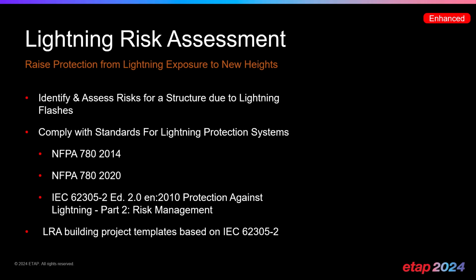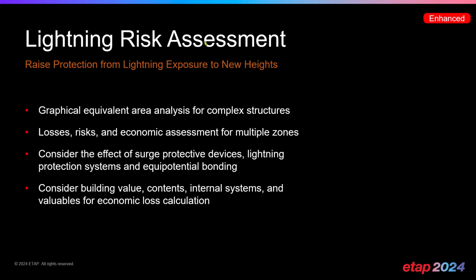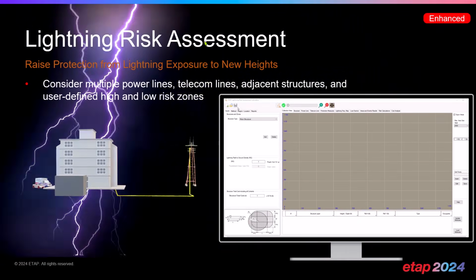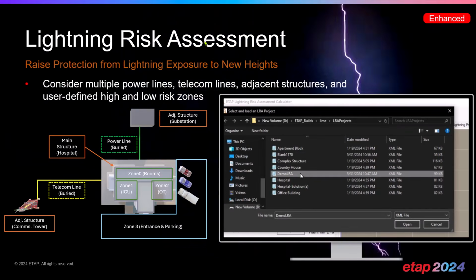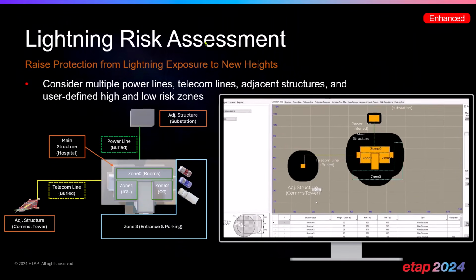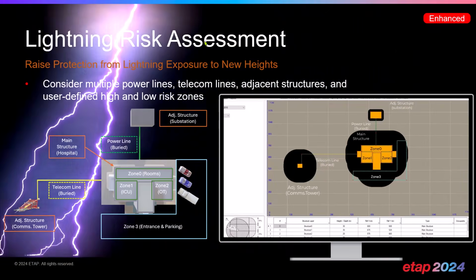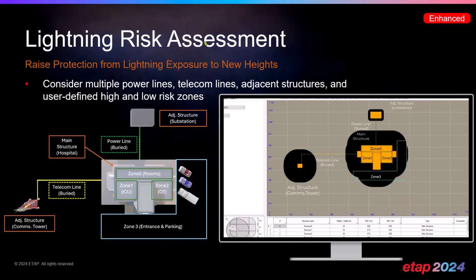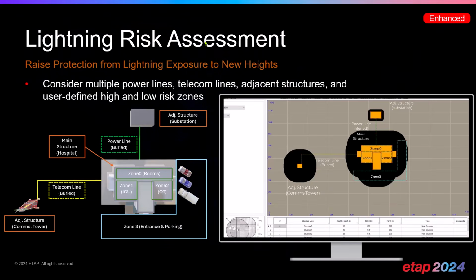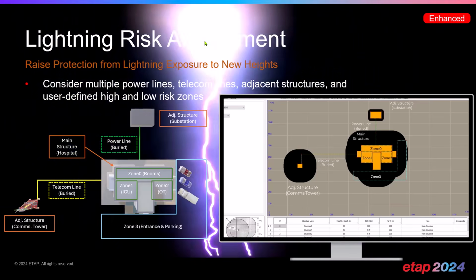And we also have project templates now based on this new IEC standard. Within the lightning risk assessment tool, we've also enhanced our graphical equivalent area analysis for complex structures. So it essentially allows you to not only consider the effect of the lightning protective devices and the lightning protection systems, but it's actually done for multiple zones at the same time. So what does that mean? We can take multiple power lines, telecommunication lines, adjacent structures, as well as user-defined high and low risk zones, combine them together into one system, and then analyze that one system all at the same time, versus analyzing each zone individually and then coming together to perform an overall analysis of the lightning protection system.